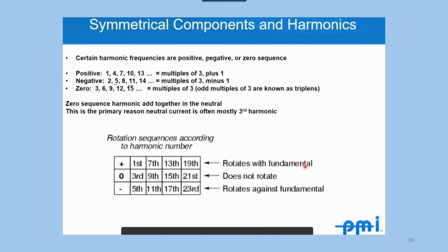So the positive sequence rotates with the fundamental, which is good. The zero sequence does not rotate. And then the negative sequence, that I mentioned before, where I had different voltages on two phases, those are actually rotating against the fundamental. So that's bad.